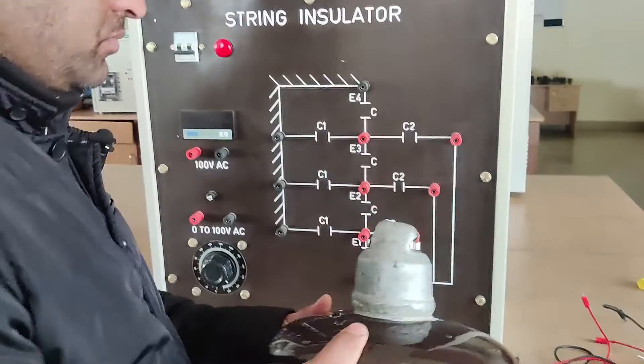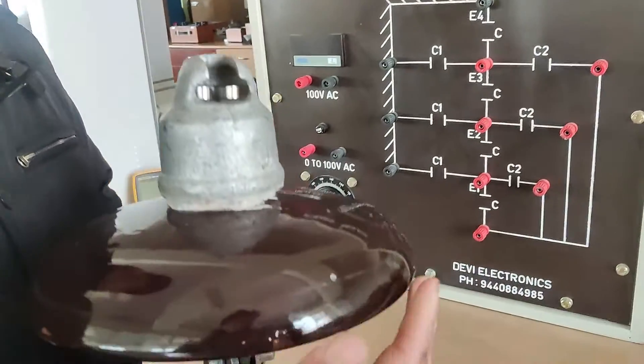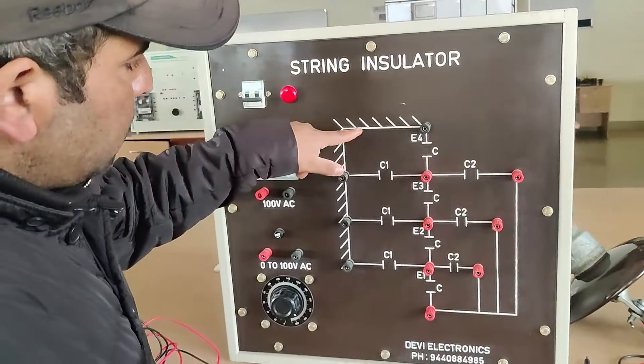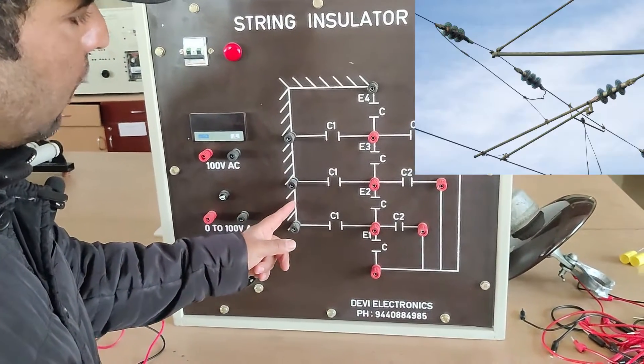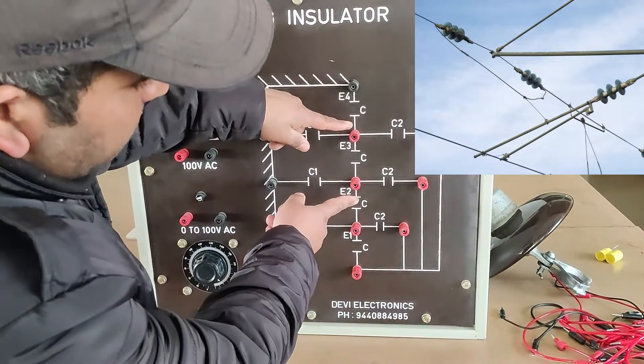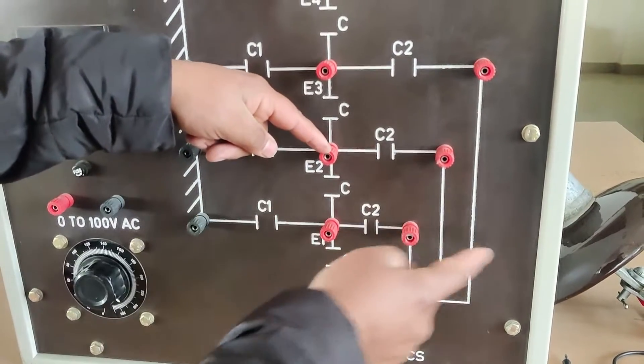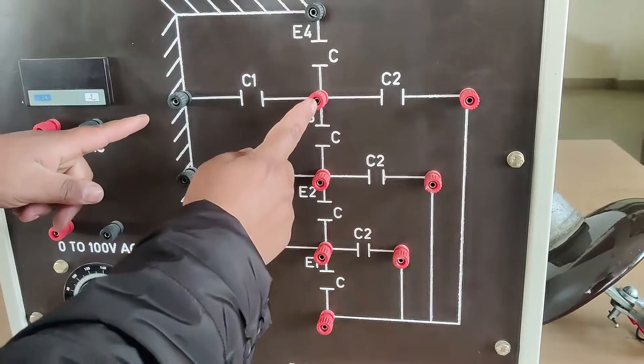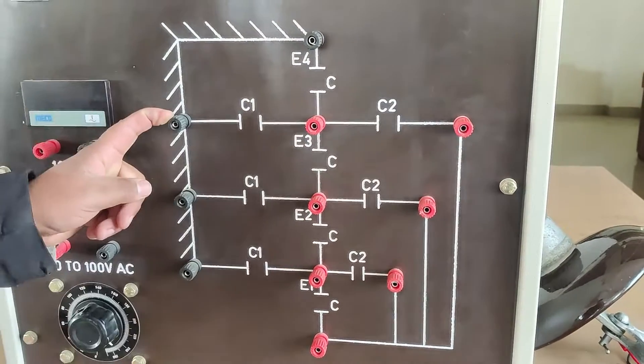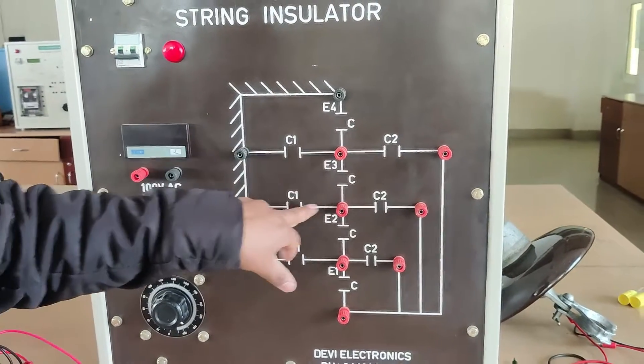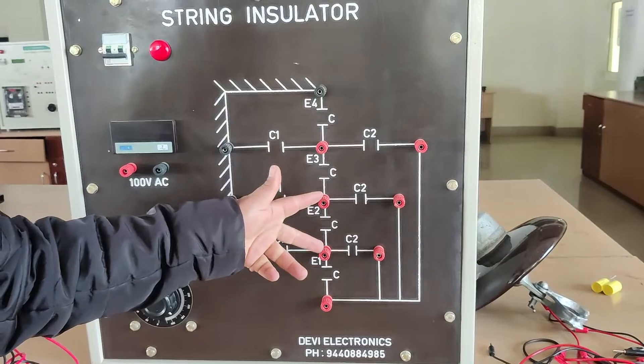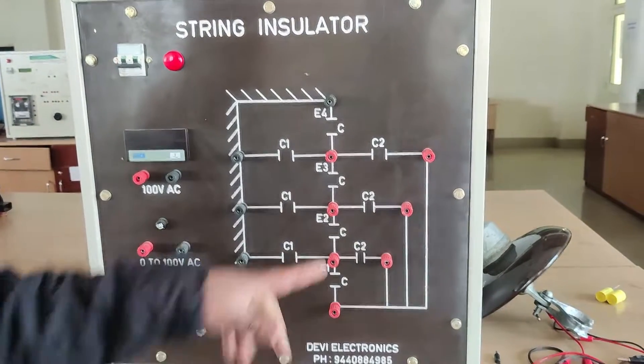Simultaneously, since this series of discs is connected on the other side to the cross arm of the tower structure, there exists a capacitance which we call earth capacitance. So we have two types of capacitances: the pin-to-pin capacitance, where the disc is the dielectric medium — that is the main capacitance — and another capacitance between the pin and the tower structure, which is the earth capacitance.